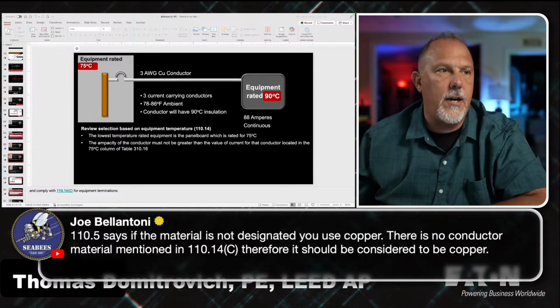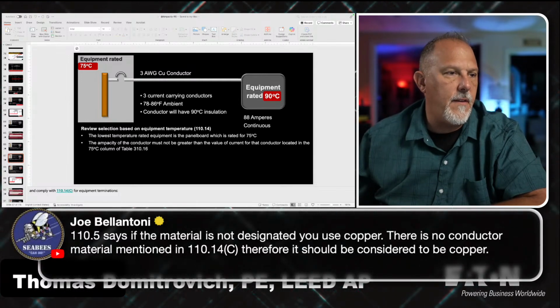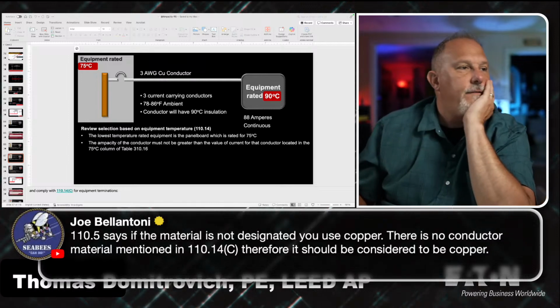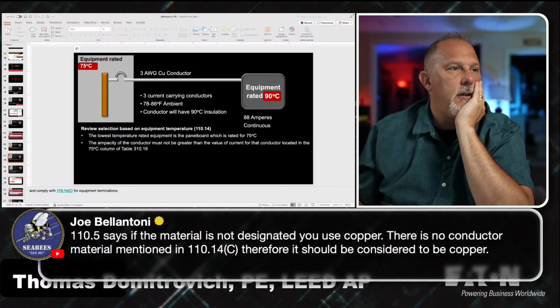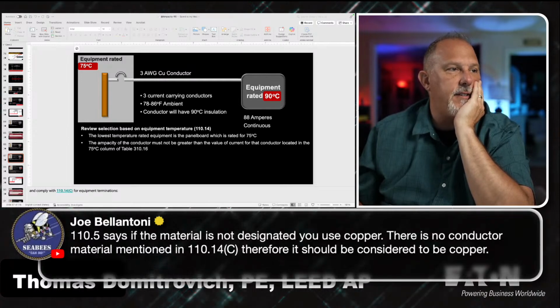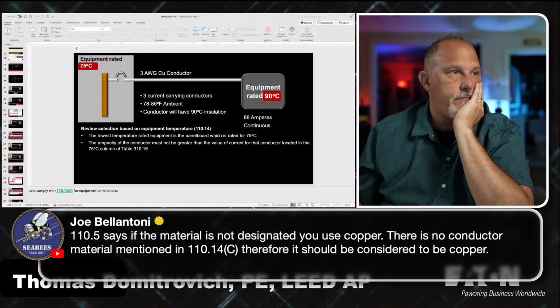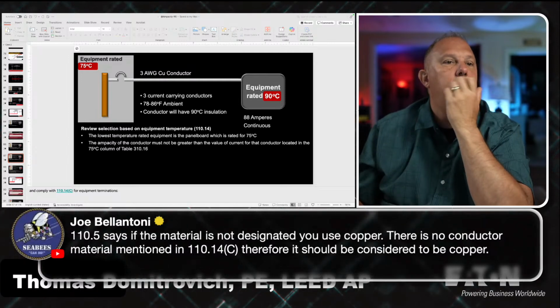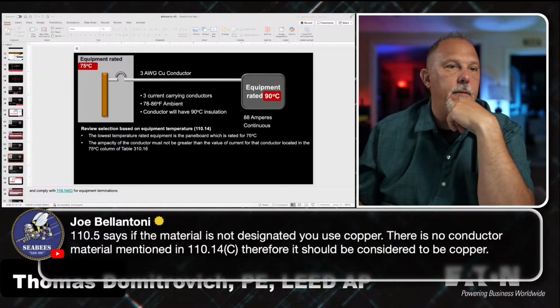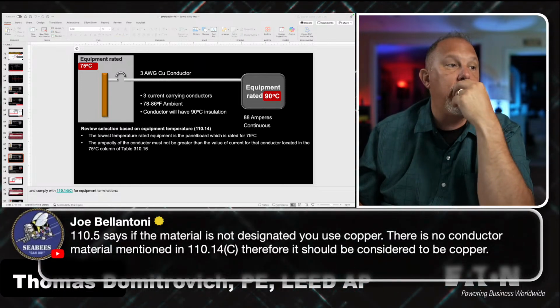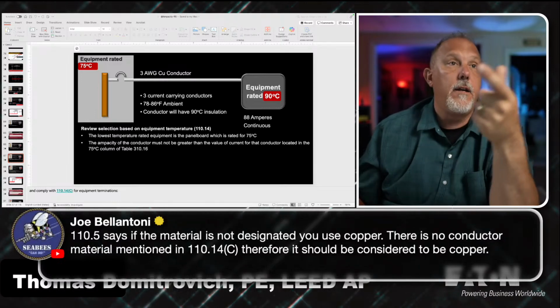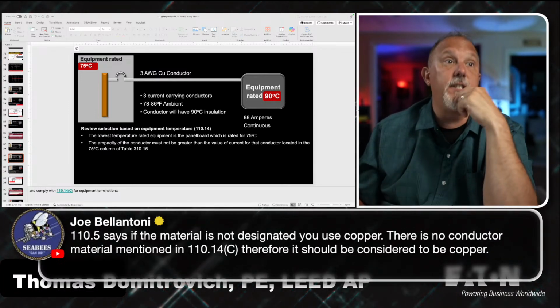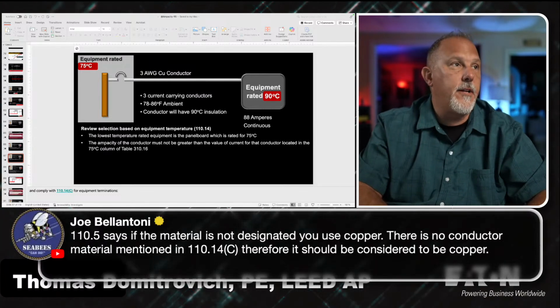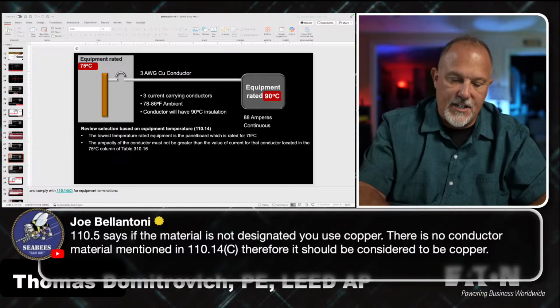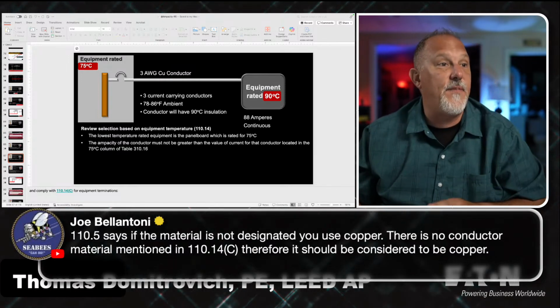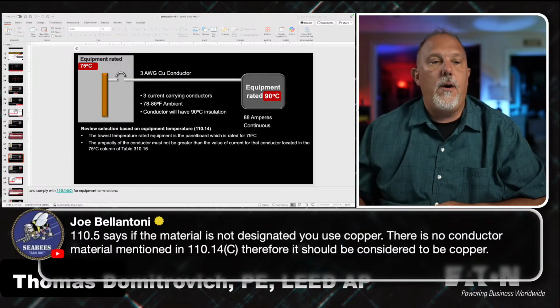If I look at a 14 copper, let's go to 310. If I go to a 14 copper in 310.16, the equivalent copper clad aluminum is not in the list. You know where it is? It is in the 2026 code, at www.nfpa.org/70, where next panel 6 fixed this issue. Oh boy, this is nice.